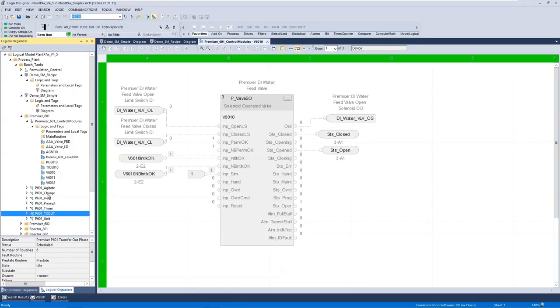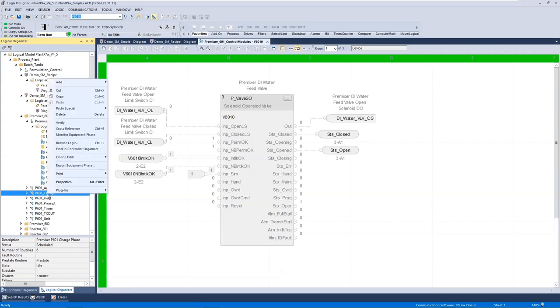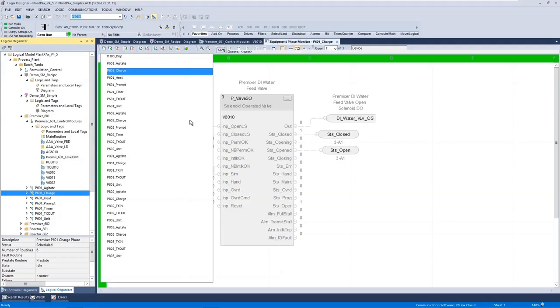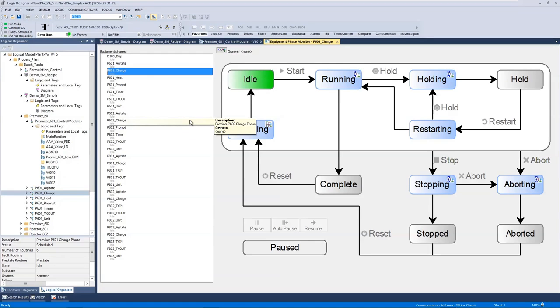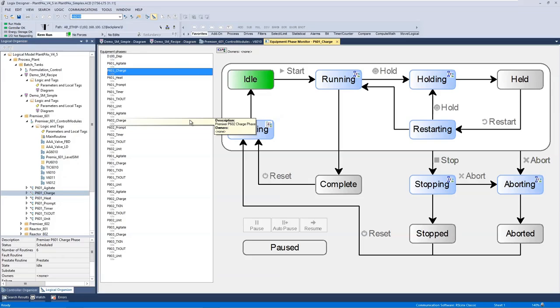These are implemented using Phase Manager, which is built into Logix and is a special type of program. What Phase Manager gives you is a built-in S88 equipment phase state model into the firmware of the controller. So here we can see that state model. We've built that into the firmware so it understands these states. It understands that if I'm in running, I can only hold and go into holding, or I can complete, or if I receive a stop and abort command, I can go into stop and abort. And if I'm in the abort state, for example, I can only process a reset command to go into idle. So the firmware takes care of that. You don't have to code that into your logic.